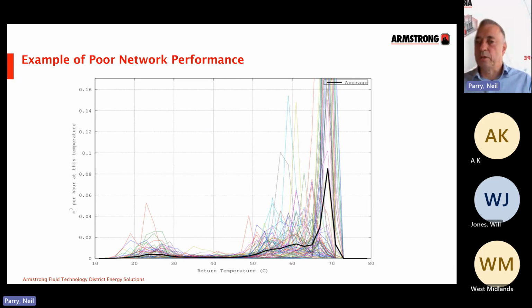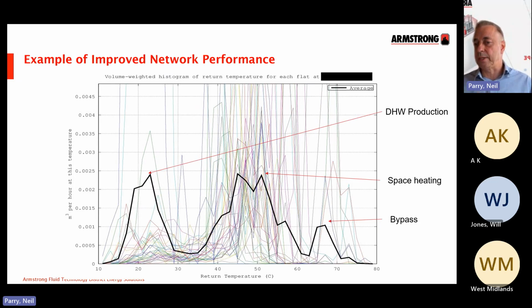and move to something more like this. So this is another building, and what you can see now are some distinct peaks in different areas on the graph. The peak on the far left-hand side is the return temperature you're seeing from the HIU when it's in domestic hot water demand mode. So you're getting a real high delta T there, 80 flow and a roughly 21, 22 degree return. So a very large delta T, great for network efficiency.